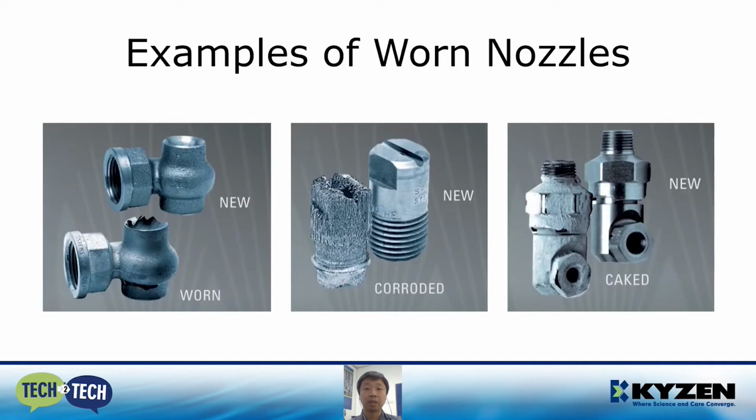But while inspecting the nozzle, we might see the nozzle in this condition. It could have worn after a long period of usage. It could be corrosion, where the nozzle material is just too sensitive to some cleaning chemistry. For instance, some steel material nozzles are sensitive to high pH cleaning chemistry. Therefore, nozzle material should be taken into consideration to avoid this happening.